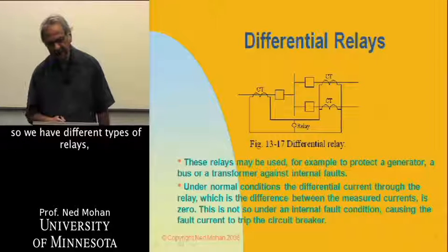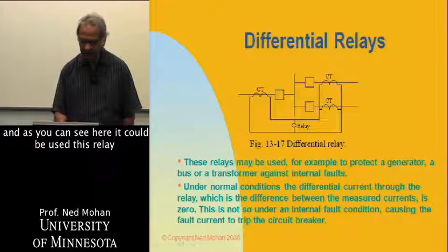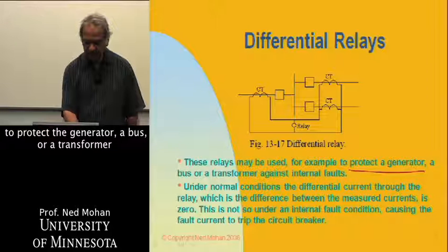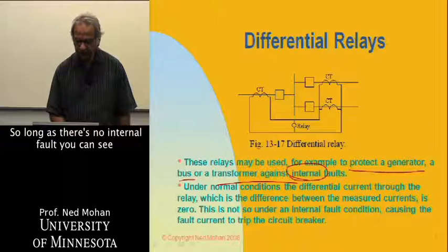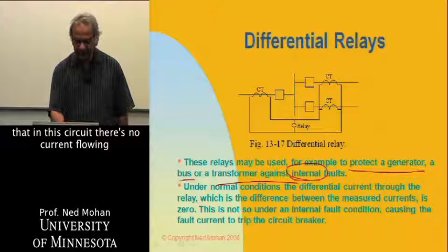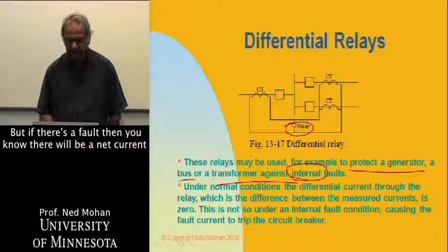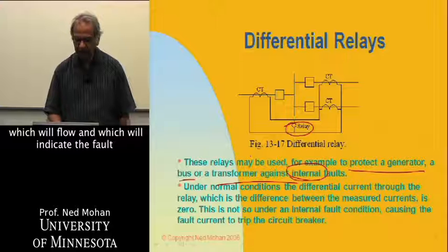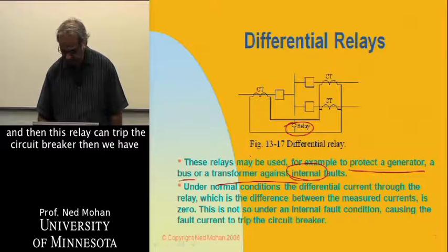We have different types of relays. One is a differential relay. As you can see, it can be used to protect a generator, a bus, or a transformer against internal faults. So long as there is no internal fault, there is no current flowing through this relay. But if there is a fault, there will be a net current which will flow and indicate the fault, and then this relay can trip the circuit breaker.